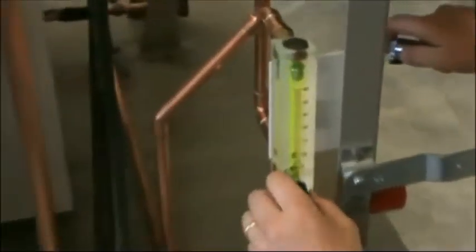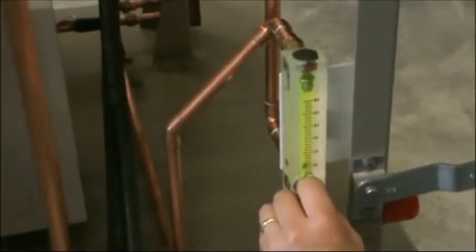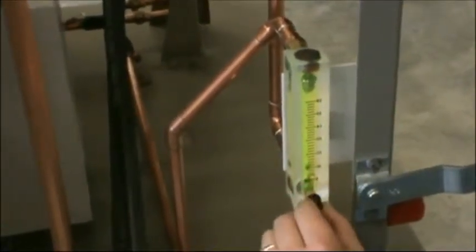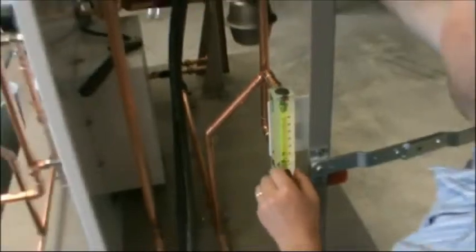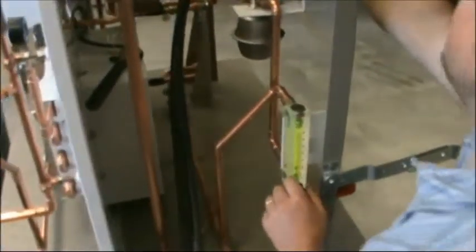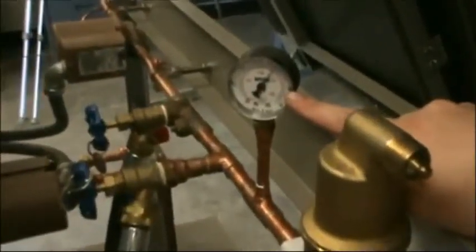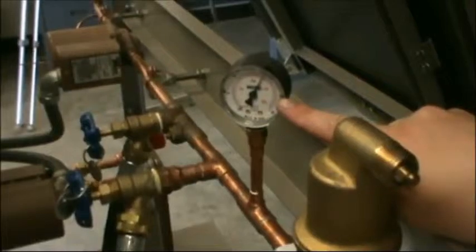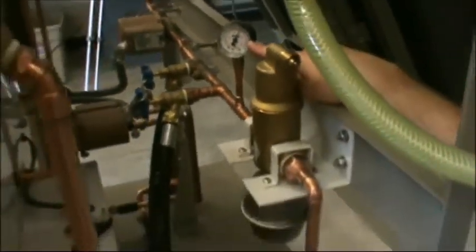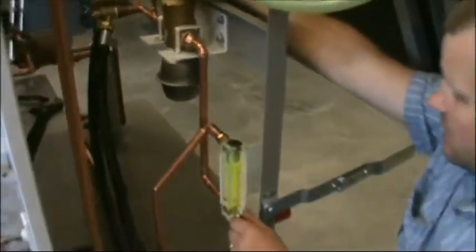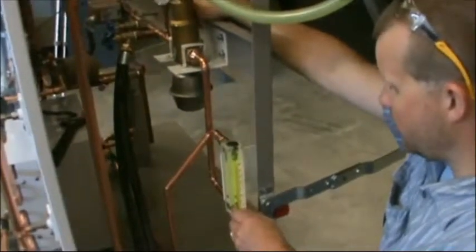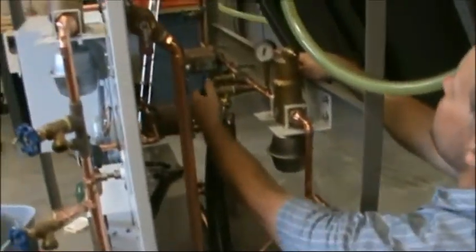You can hear that flow is causing that meter to exceed its pressure, so I'm going to open this back up to full pressure. A couple things to notice: as you see this gauge up here shaking, that tells me that there's still some air into the system. So I'm going to open the flow restriction on my flow meter all the way, so it should be all the way open, and then I'm going to just keep running this.